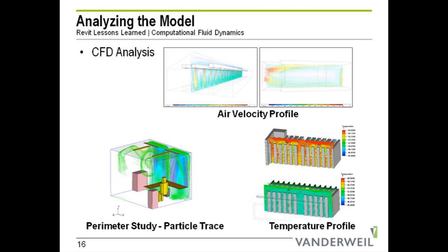The bottom right pictures here were actually for a pharmaceutical storage facility, where it is very important for them to figure out what the temperature was going to be, not only for the entire space, but they wanted to make sure that they didn't have any hot spots, that they weren't going to have any spaces where product being stored was going to go bad or spoil. And the top one, red is hot, green is cool. You'll notice that in these two different air distribution methods, we were able to see that one method was very ineffective, while the other method was very effective.